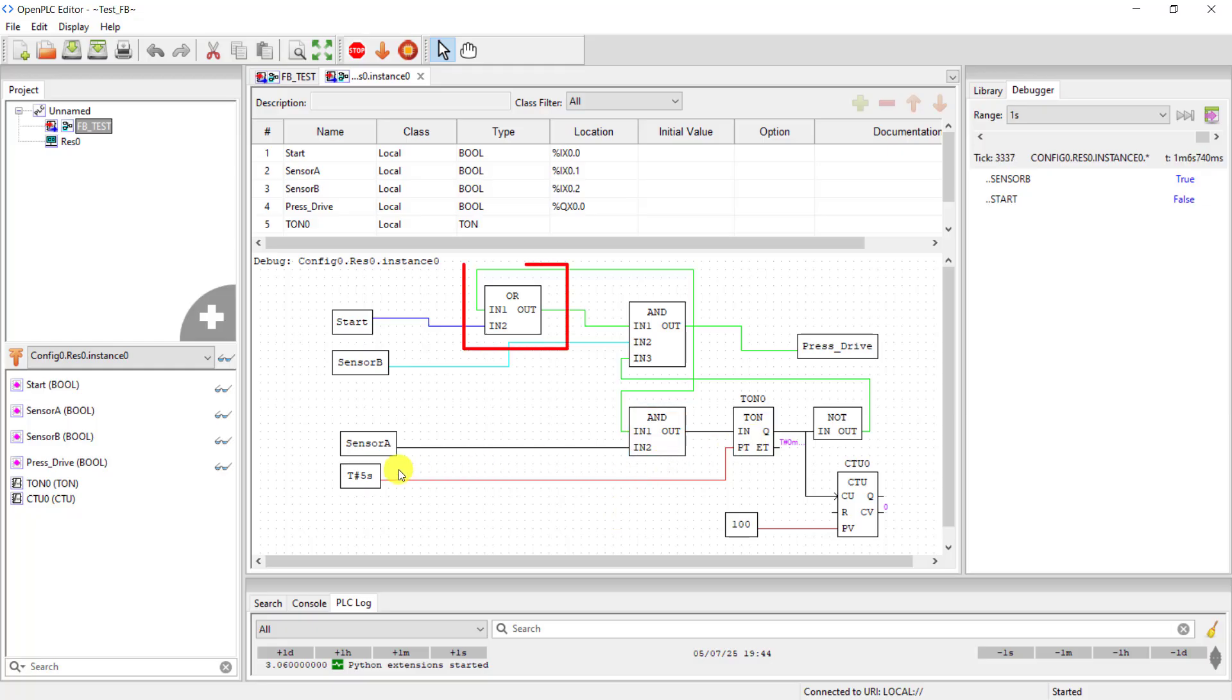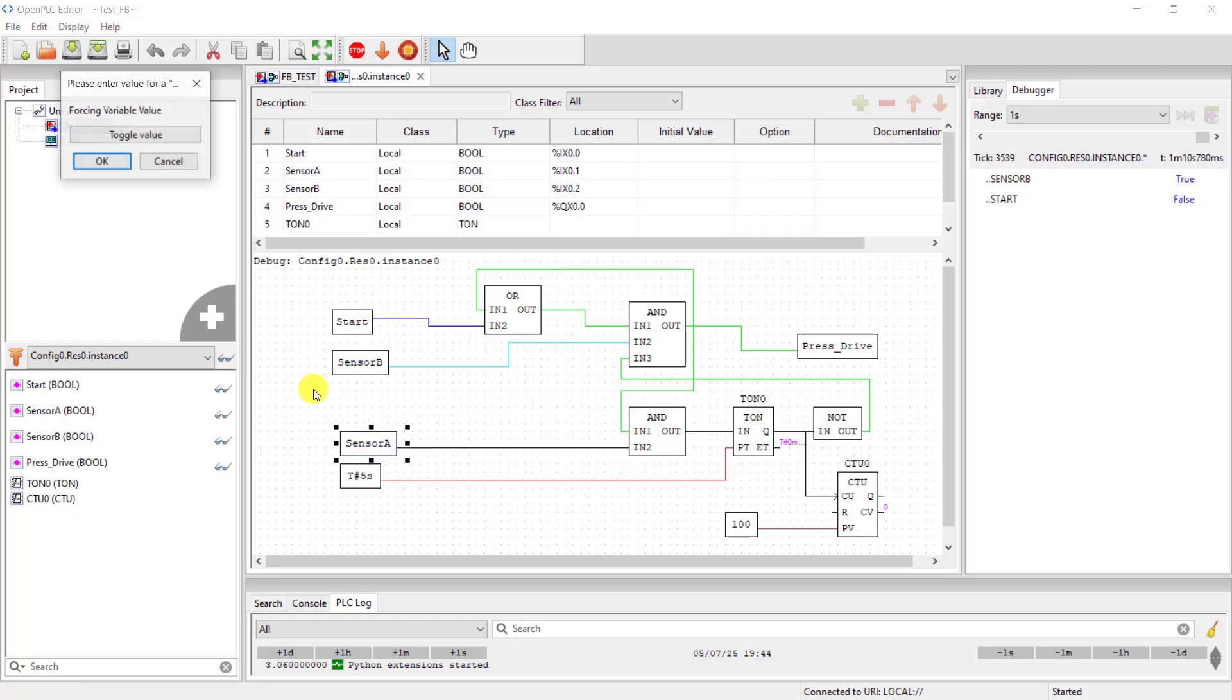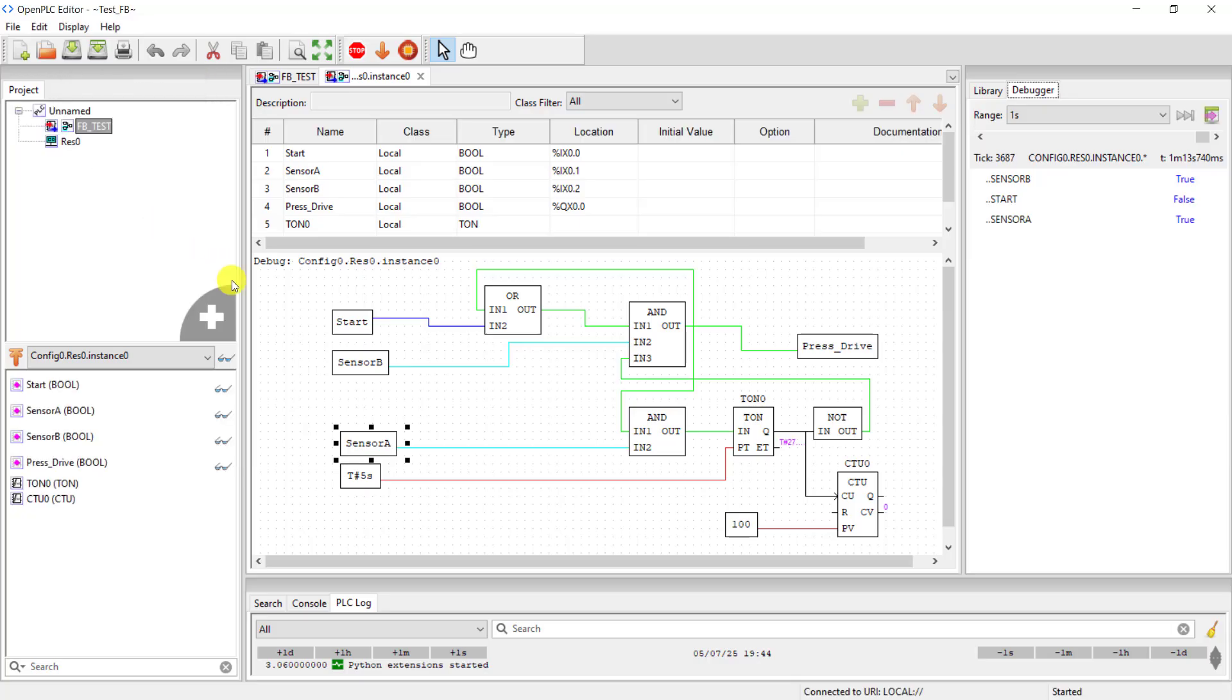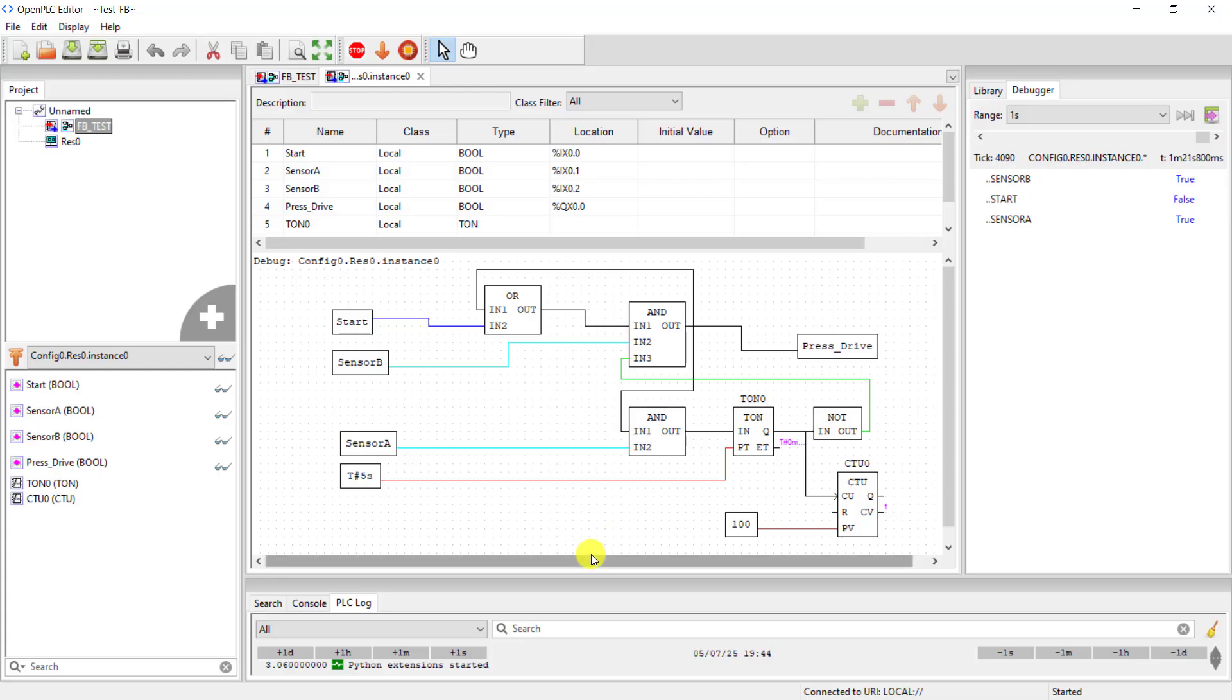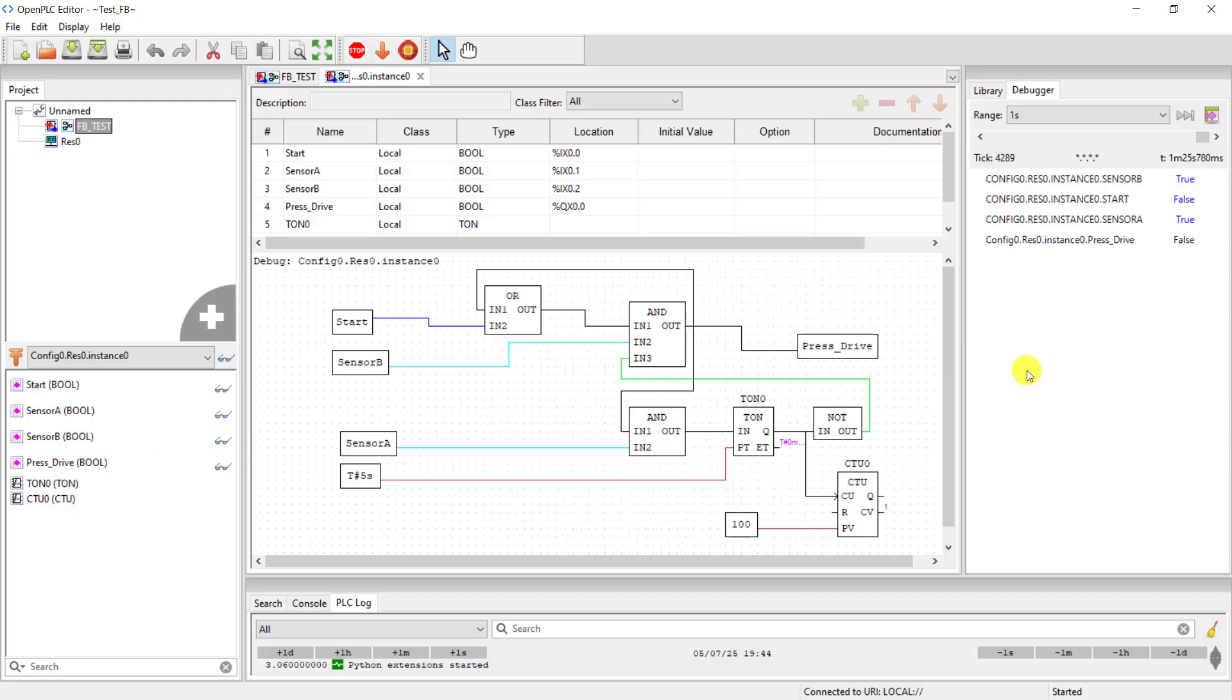I toggle it back off - remember it's a momentary switch - we can see the output is still on by the help of the OR gate that we use as a hold on. Now I activate this fully extended switch of the cylinder and we can see the timer has started counting. And immediately the time is due, we can see that the process has stopped. And now go or monitor the output and we can see the output has gone to false.